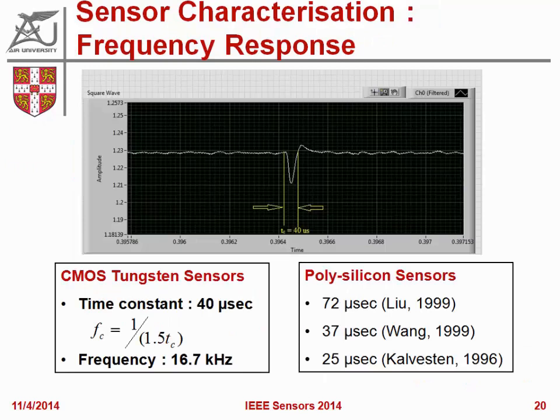For temporal resolution, we were able to achieve a frequency response of 16.7 kilohertz, which is good enough. Anything beyond 10 kilohertz is good enough for most fluids.